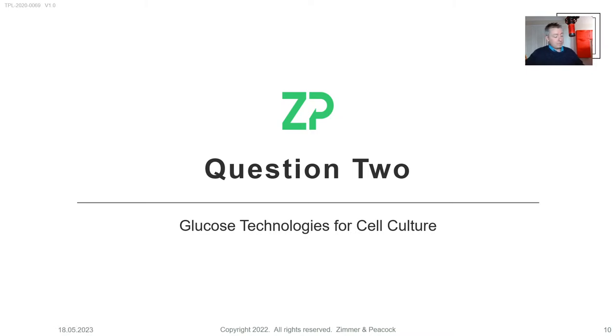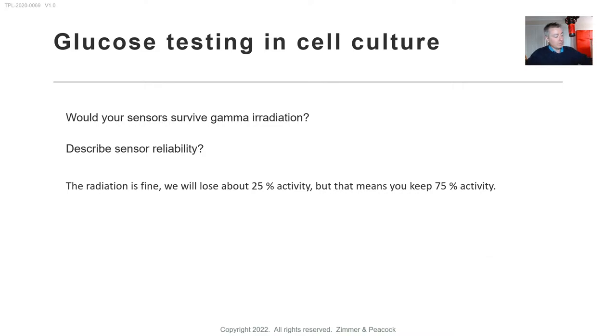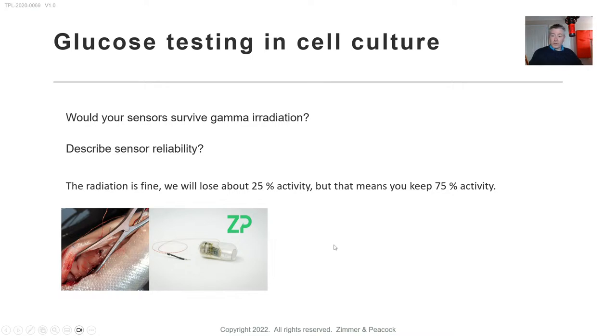Question number two came in about glucose sensing. At ZP I started my career in glucose sensing around 2001, and we started ZP nine years ago, so we have a long history here. One question was whether our sensors survive gamma radiation. Yes — sterilization options include EO (ethylene oxide), EB, and gamma radiation. I would not suggest autoclave for biosensors due to high temperature and high humidity. Gamma radiation is fine as long as you keep the dose down.